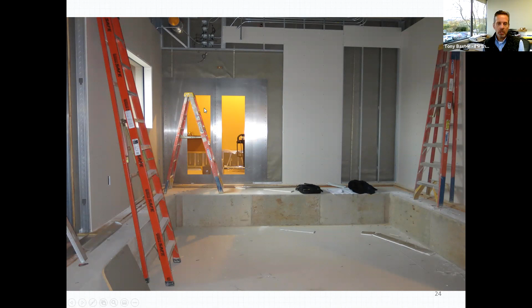The blue line is the isocenter, where the MRI would sit, the center of the isocenter on that 20-inch slab, and the red is on the floor. You can see the curves match pretty well, there wasn't any real difference between them. Maybe these two are the worst, and maybe the 20-inch slab, shown in blue, is actually a little higher than the floor.